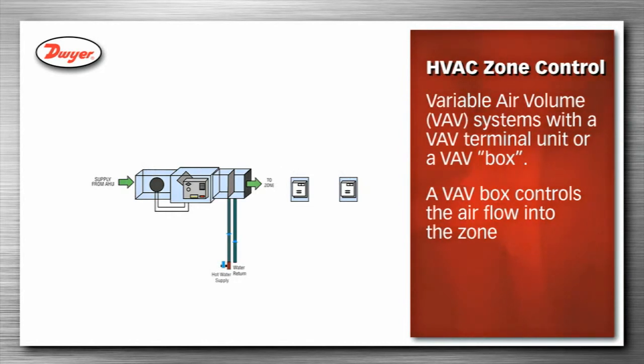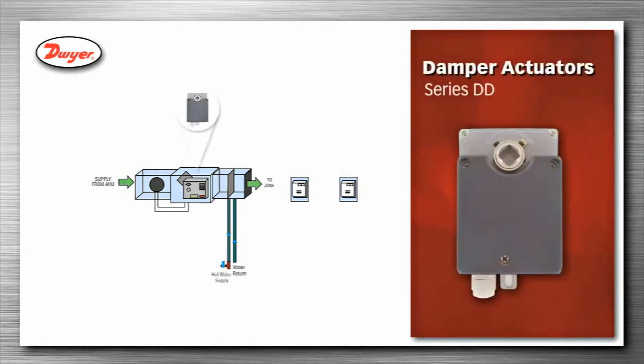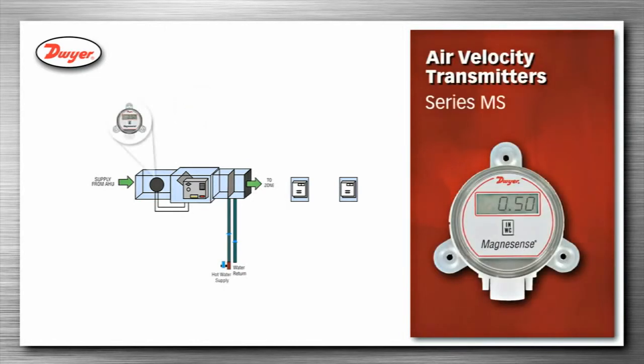Dwyer offers several products used in zone control. Damper actuators, series DD, are used to control the amount of air added to the zone by opening and closing the air duct via a damper. An air velocity transmitter, series MS, differential pressure transmitter, is used to monitor the duct airflow. The series MS has square root extraction for direct air velocity indication.